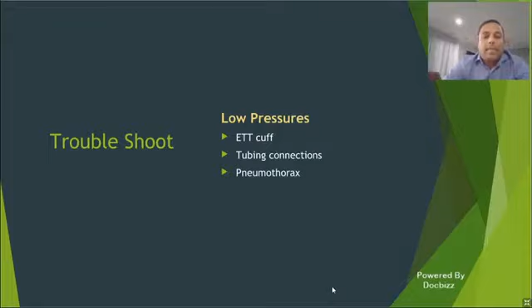Okay, so once we put patients on the ventilator and their oxygen is still low, what are the things that we can do on the ventilator no matter what mode they're in? One of the simplest and easiest things we know is to play with the FiO2. So if their oxygen is not already set at 100%, that's the first thing to do, is to go up on their oxygen. Simultaneously, you increase the PEEP as well. The ARDSNet protocol again gives you, for what FiO2, how much PEEP needs to be delivered. There is a high PEEP strategy and a low PEEP strategy, and based on the table we can set the PEEP according to where the FiO2 is going.